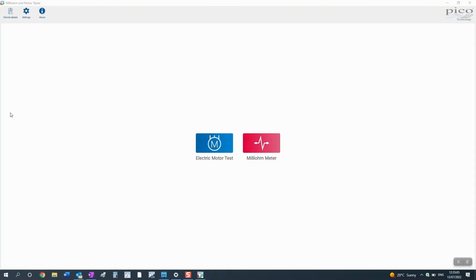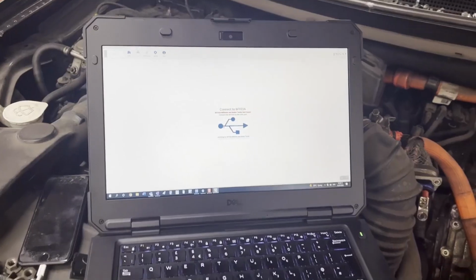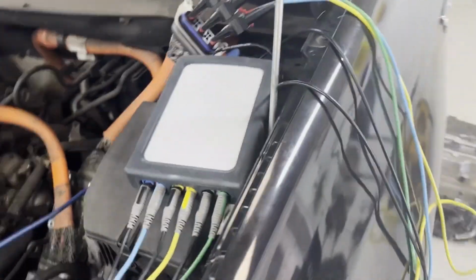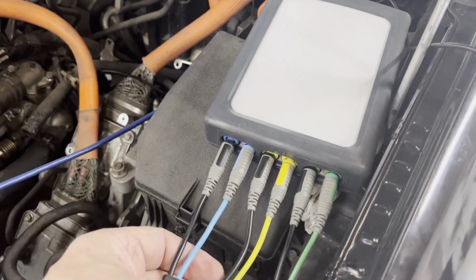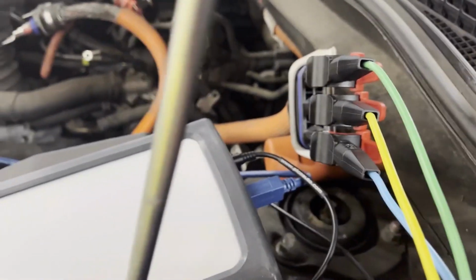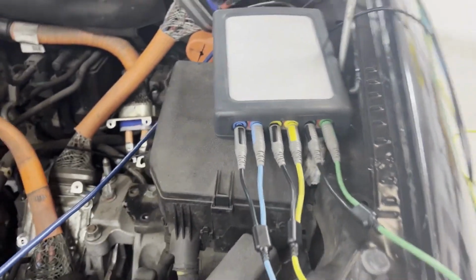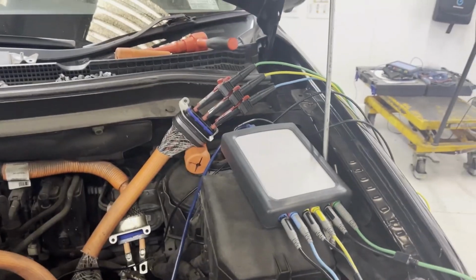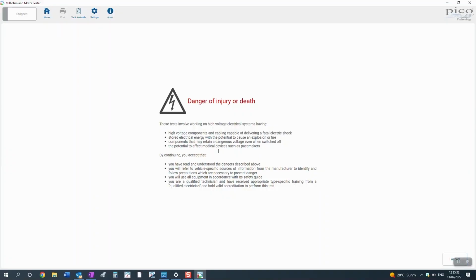So here we have the software. This is the Milliohm and motor tester software, and we want to perform an electric motor test. So double click on the icon. It's a USB device. We'll follow this around. And here it is. Milliohm meter motor tester USB. And you'll notice six leads on the front. It's actually a three-wire test we're going to perform. The software now is asking us to accept the message and also acknowledge the message as well, more importantly. And here is the menu.